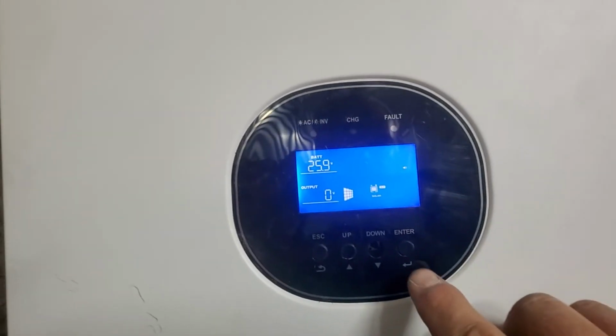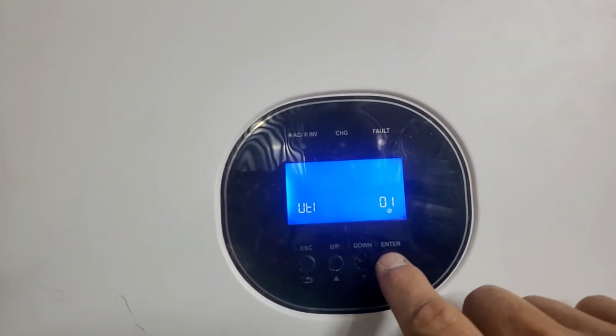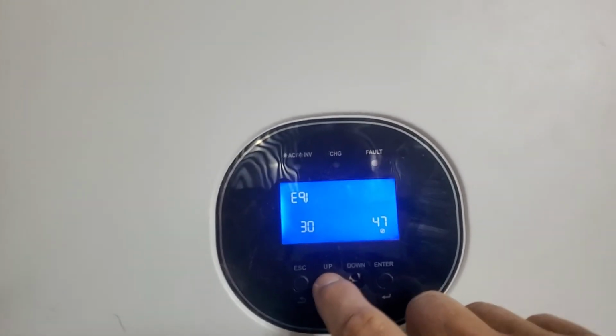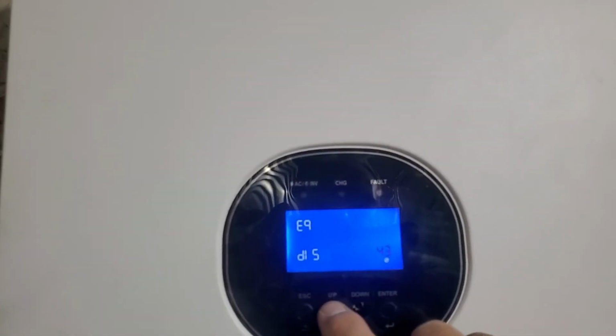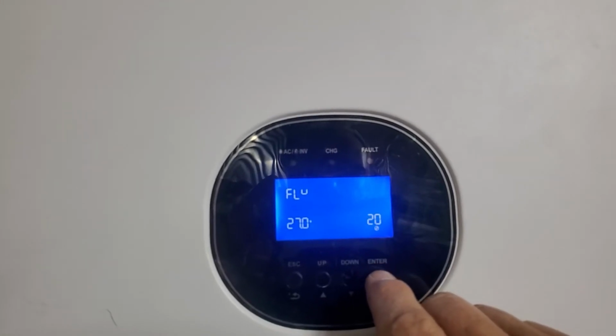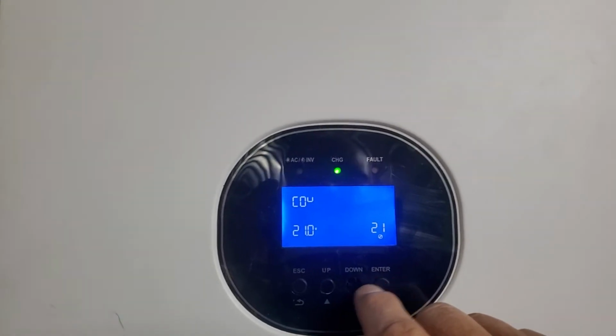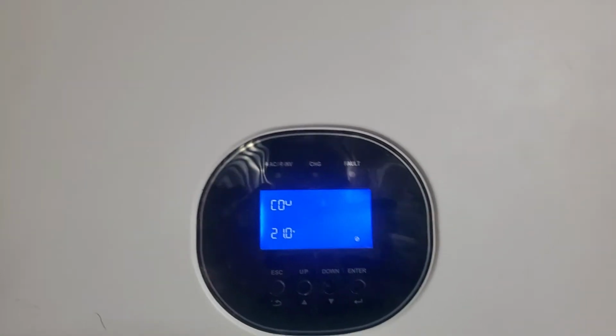Now what I'm going to do quickly is set my... and you see that one button is missing on this thing, it's probably a bad choice to use. My float voltage and bulk voltage, look at that, bulk voltage is set to 27 volts. I've got to drop that down, otherwise it's going to overcharge the battery again.